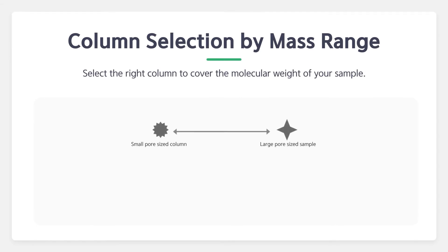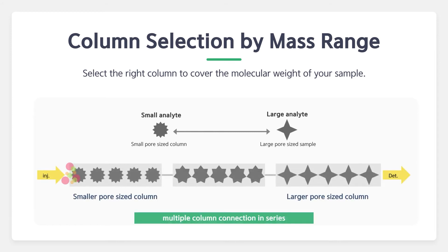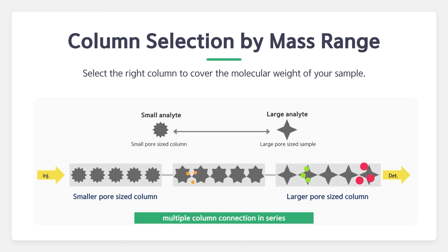Select the right column to cover the molecular weight of your sample. If your analyte is small, select a small pore-sized column, and if the analyte is large, select a large pore-sized column. If you have a wide range of molecular weights in your sample, multiple column connections can be utilized to determine the accurate molecular weight distribution and increase resolution.